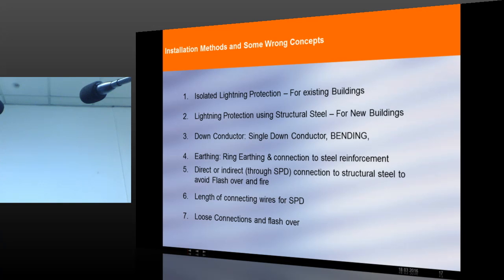See, when we go for a site study or when we make a real installation, some of the points which we always discuss, I want to explain. For an existing building, we can only have an isolated lightning protection. Isolated lightning protection means, say for example, a down conductor which is coming. The down conductor has to be placed on the wall. It is not integrated inside the wall, it is placed on the wall.